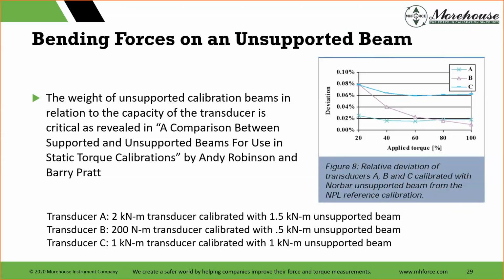I mean, the data on A, the 2 kilonewton transducer calibrated with a 1.5 kilonewton unsupported beam, you can see the error 0.02. This is just comparison. The best they were getting on this device was like 0.02. A lot of people here are claiming like 0.16, 0.12. I see a lot of scopes where they're claiming this, but this case, Norbar makes fantastic arms, and this case shows an error of 0.02. But hey, let's look at the other beams.